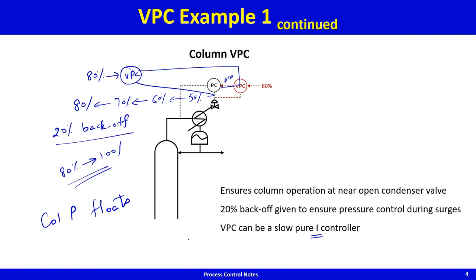Because the column pressure floats, you will have to use pressure-compensated temperature set points. In distillation, instead of controlling composition — which is difficult to measure — you control tray temperature. The idea is that if you control a tray temperature at a given pressure, a rising temperature indicates heavy component accumulation or decreasing light component, so temperature is an indirect reflection of composition.